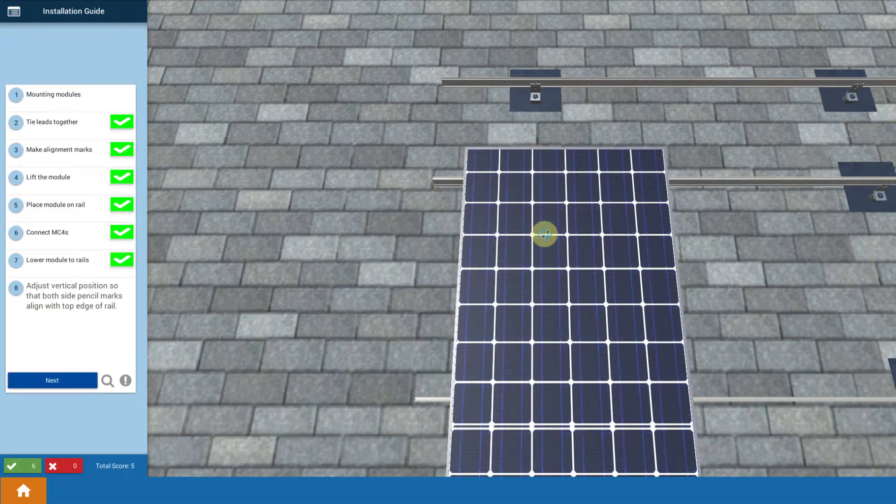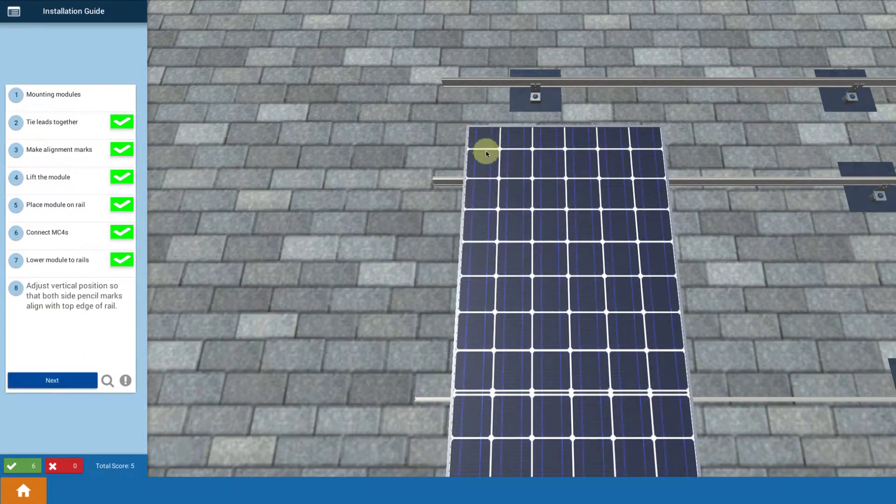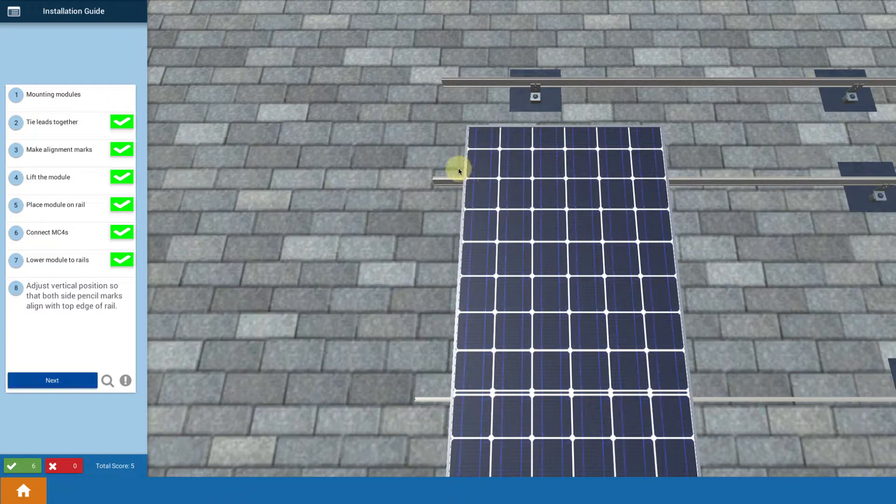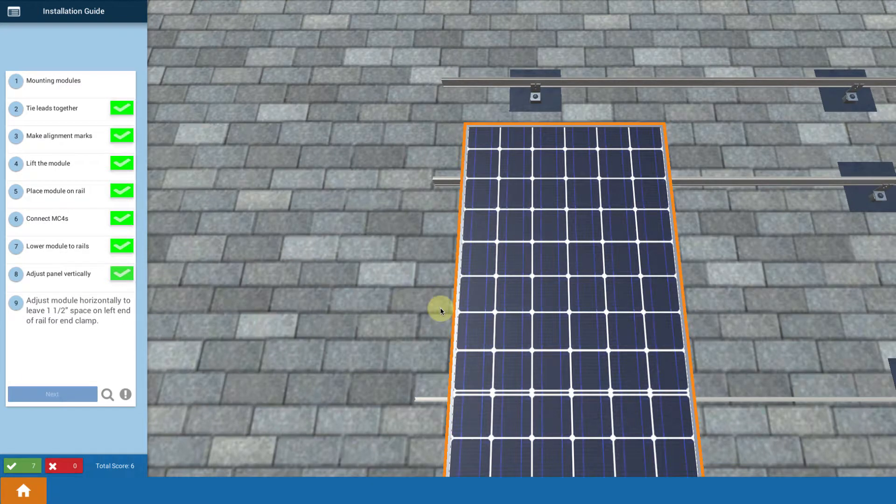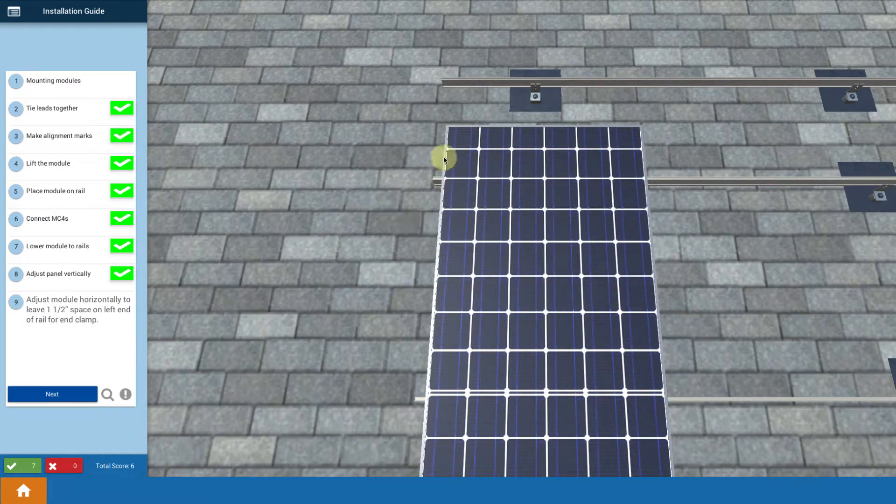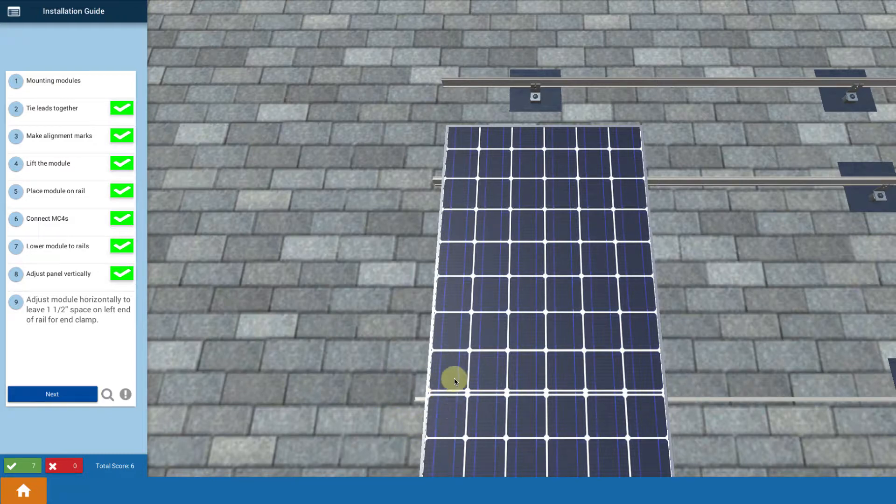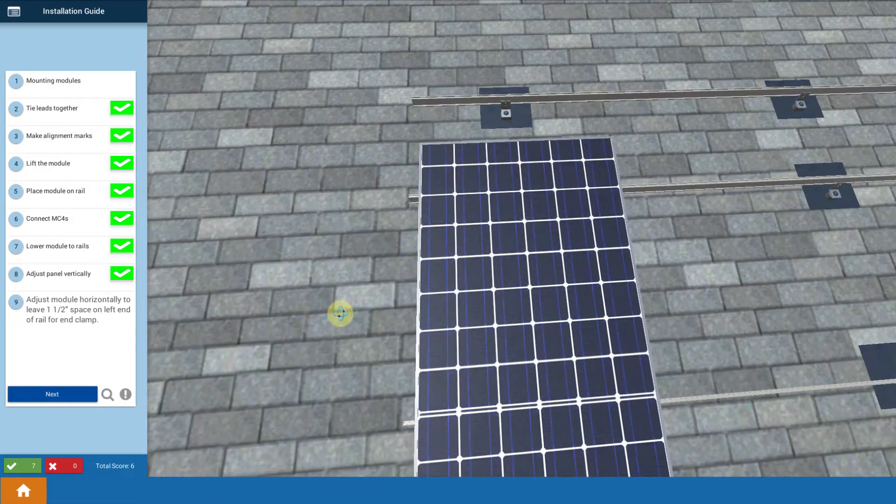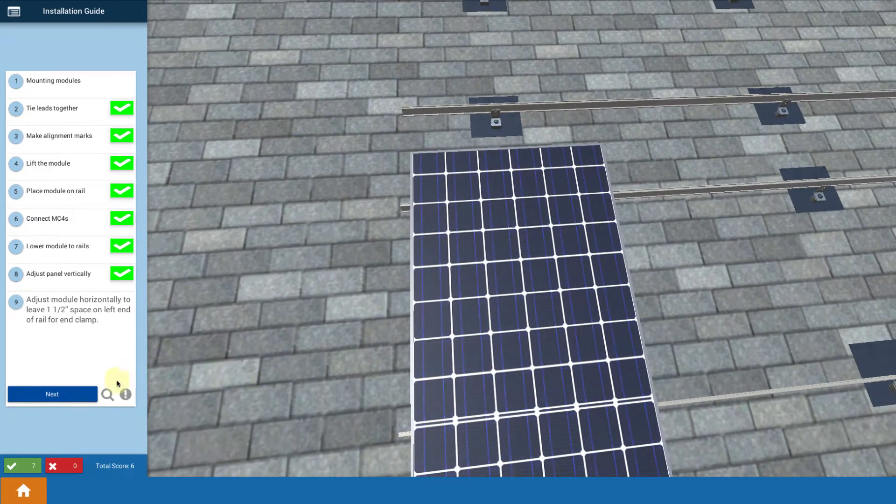Then you want to adjust. So you touch the module and you adjust it up until that 12 inch mark on each corner gets aligned to the rail. And then you're going to touch it and move it over to give yourself roughly about an inch and a half here at the end of the rails. That's enough room for the end clamp that you're going to put on.